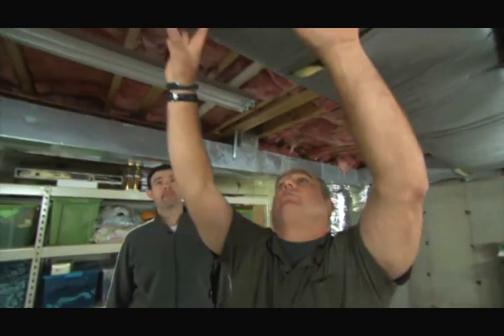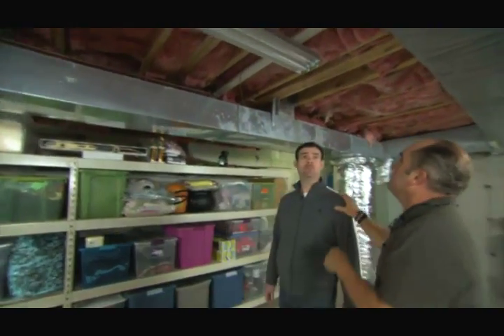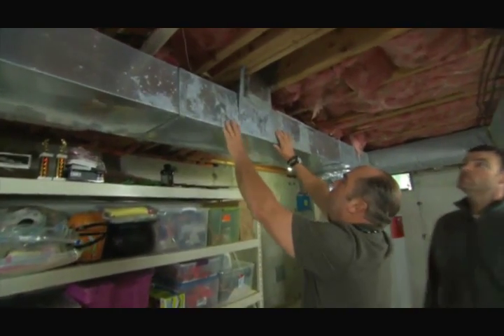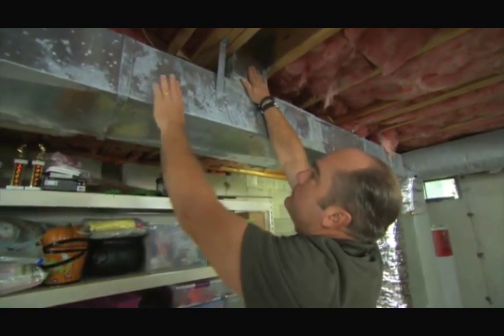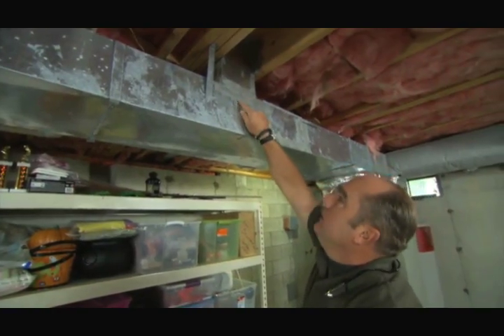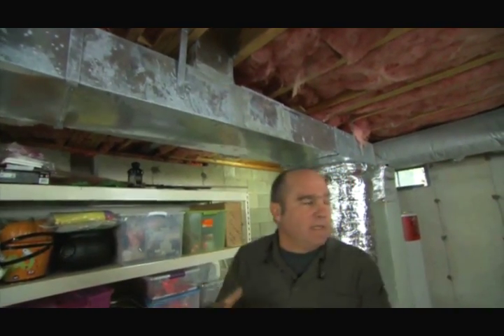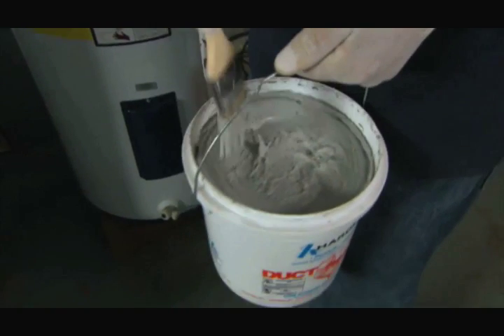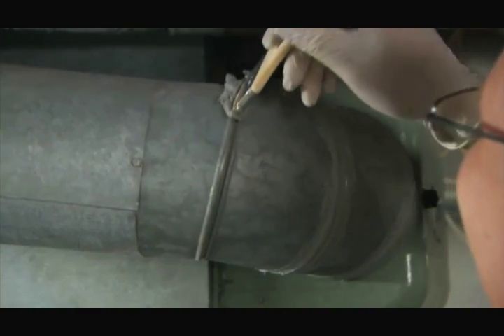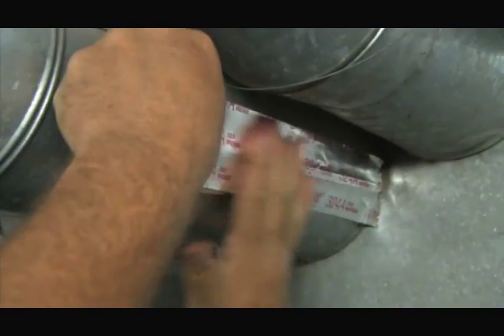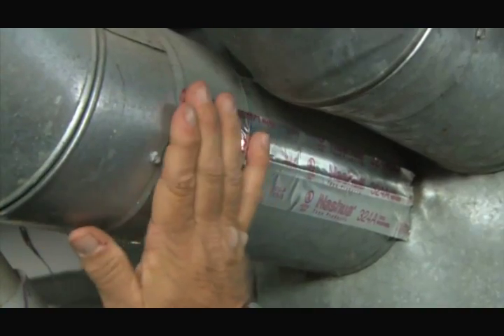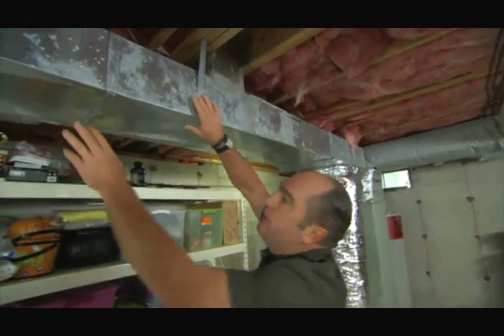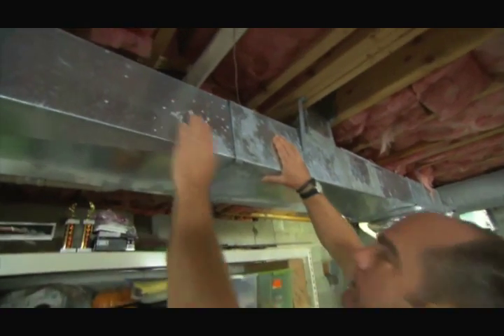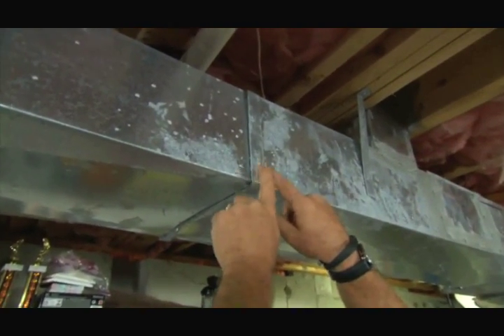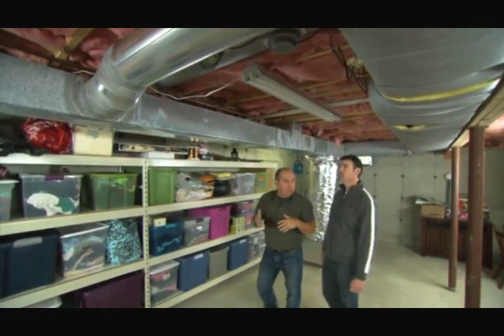Okay, so this is the supply trunk right here, insulated. But over here, you can actually see really the issue with ductwork. Here's the return coming from upstairs, here's the return right here. And when these come together, you can see that the installer has sealed this with a mastic, sort of a rubberized cement to seal up the joints. The mastic is applied with a brush at any place that air could ever leak out. It's messy, but it's really effective. You also could use a foil tape to seal any of the joints that are easily accessible. Look at the challenge. You've got a metal trunk, and the only thing holding it together is this metal cleat, and that's not airtight. So your system is not unusual.